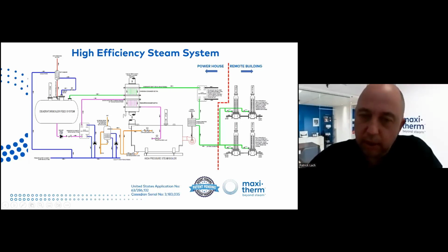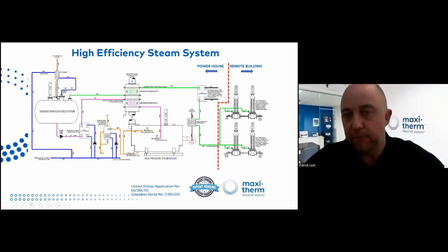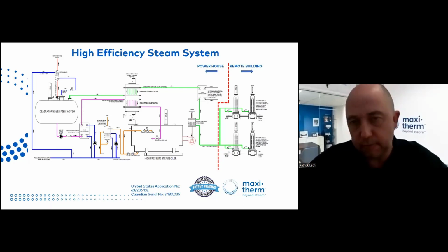And then we want to bring it as cold as possible going through an air preheater. So let's say we're coming at 110 Fahrenheit here, we can preheat the air inlet of the burner. Then maybe we can preheat, let's say we're coming back here at 90 Fahrenheit, so maybe we can preheat a domestic hot water loop if it's nearby, or a snow melt loop if it's nearby, or another building heat loop if it's nearby.